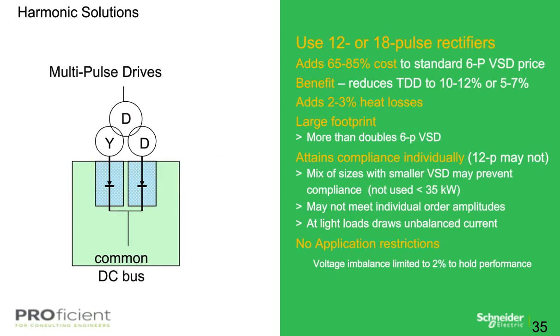Okay, so moving on to multi-pulse drives. Primarily, we're going to talk about 12 and 18 pulse rectifiers. Multi-pulse drives have really been around for a very long time, from the 50s. At that time, they were typically used to increase the size of loads that the diode rectifiers could handle. Then in the 1990s, the multi-pulse reemerged as a harmonic reduction application.